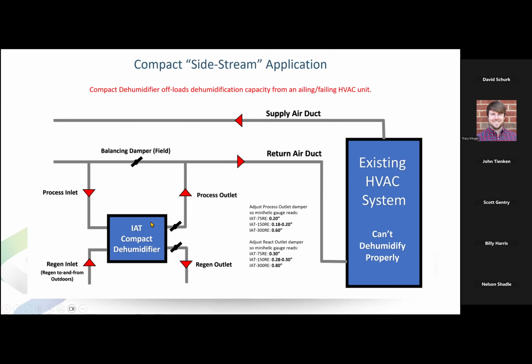Nobody's very happy. We may take these small compacts and, based on a small quantity of air, pull some air off the return, drive the living heck out of it, shove it back into the return of this existing ailing-failing system, and make it more of a dehumidifier. Take the dehumidification capacity off of this unit so that now all it has to do is respond to a sensible-only cooling thermostat and maintain space comfort temperatures, while this is responding to a dehumidistat in the space and is doing the dehumidification. And maybe now that space that at best could do 65% relative humidity is now able to do 50% relative humidity.